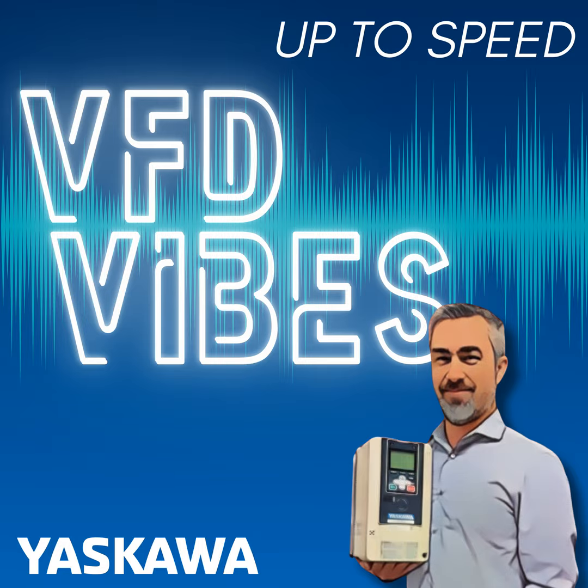So you mentioned grounding the motor to the drive. What are some of the best ways to do it? I know you can run wires in a conduit. There's these shielded VFD cables. What are your thoughts around these?